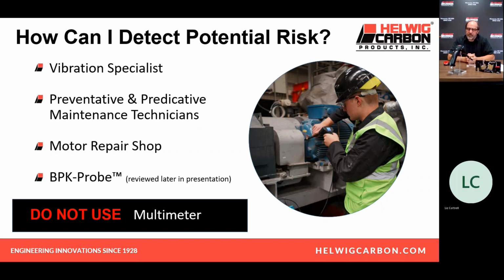detect shaft voltage? You can call in a vibration specialist. Generally, what they'll do is they will monitor your motor. They will watch for anomalies in the motor that are mechanical in nature, and they will go, yep, your bearings are fluted. Predictive and preventative maintenance guys can do the same type of thing. They'll come out, they'll monitor everything, they'll let you know there's a problem, along with your motor repair shop. After your motor has failed, you send it in.